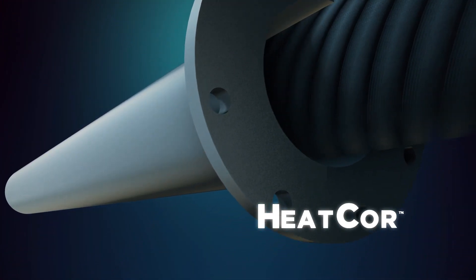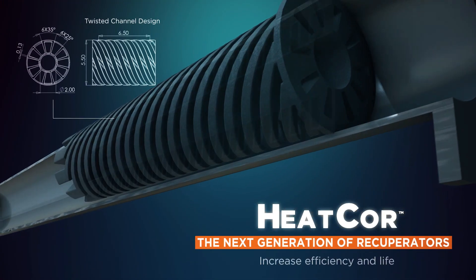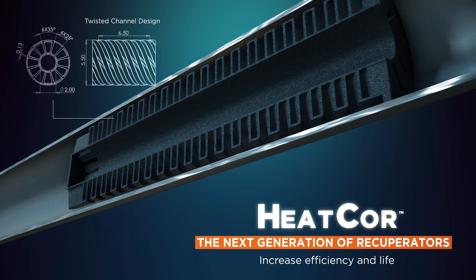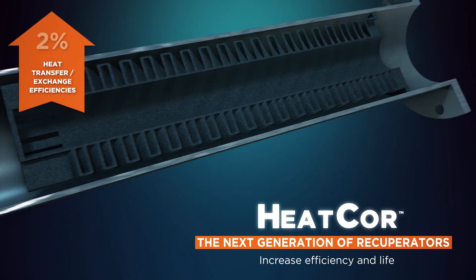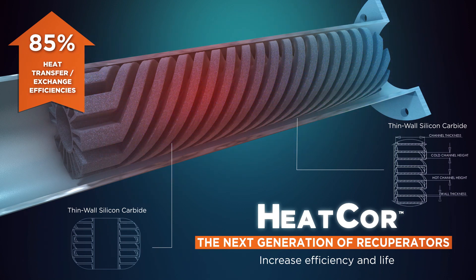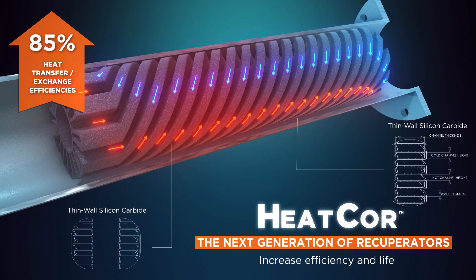HeatCor's patented twisted channel results in more than 10% energy savings, with a life expectancy greater than two times that of standard alloy recuperators. HeatCor's counter flow design is made of thin wall silicon carbide, which maximizes surface area and heat transfer to optimize waste heat recovery from the radiant tube exhaust.